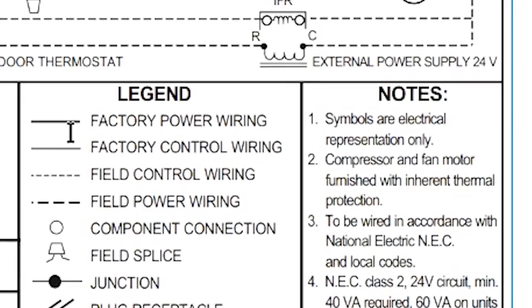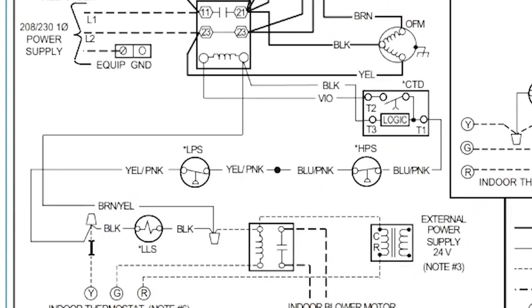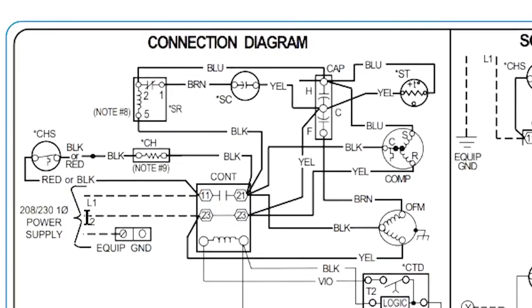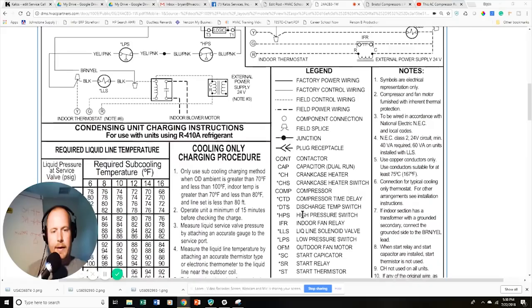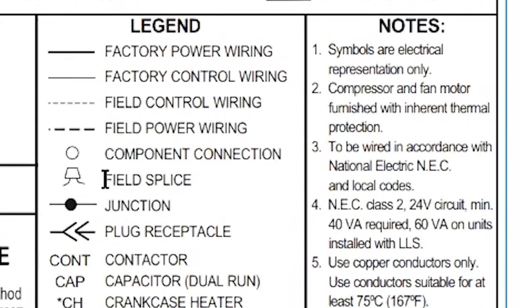These are all pretty standard things: factory power wiring is a solid line, factory control wiring is a lighter solid line, field control wiring is a dashed line. When you see dashed lines, those are lines you would actually have to add in the field. Solid lines are wires inside the appliance itself — the dashed lines here are your high voltage lines that you're wiring in.